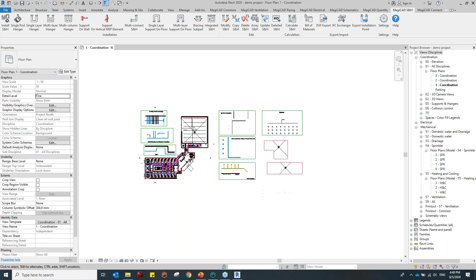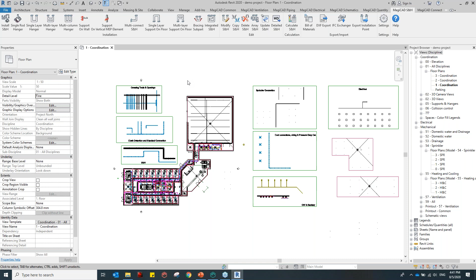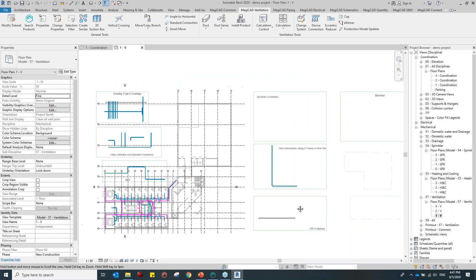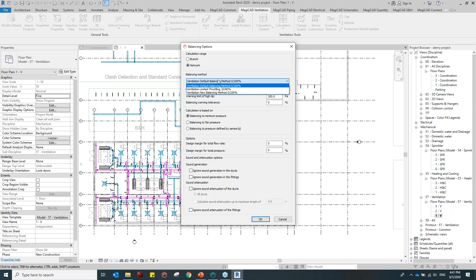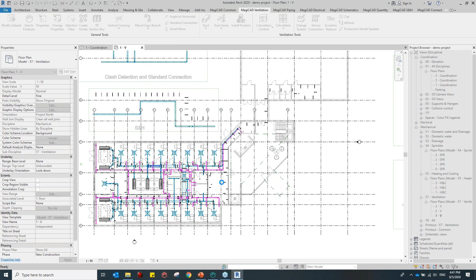Let me show you some sound calculations since somebody is asking. Let me go to the ventilation systems. So for example, if you want to do the sound calculation, what you need to do is run a sound calculation, specify the balancing method for the sound, then select the network, and it will generate the sound calculation for the ducting.